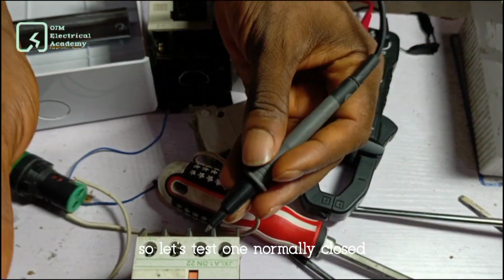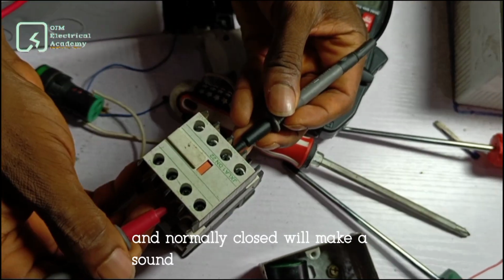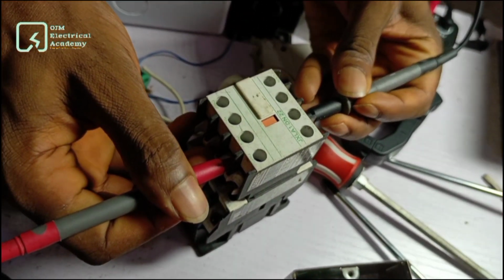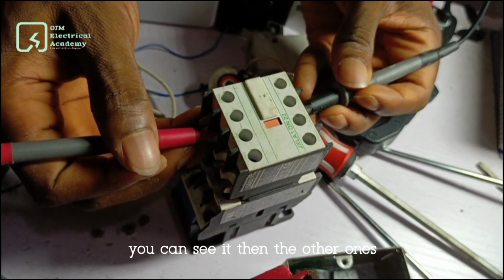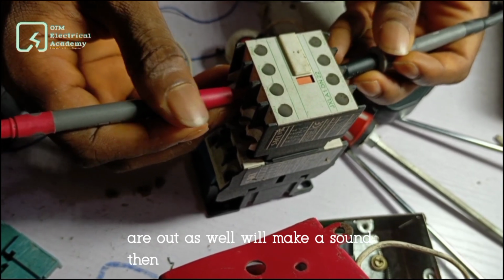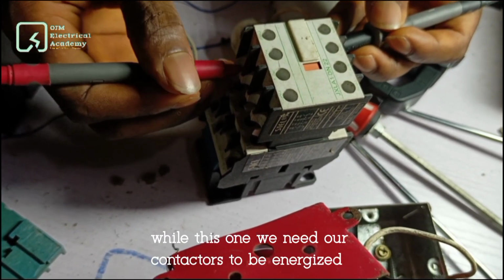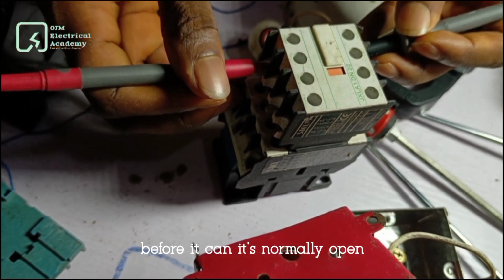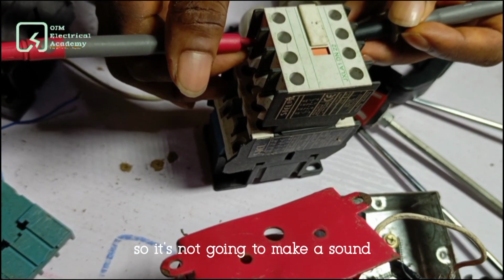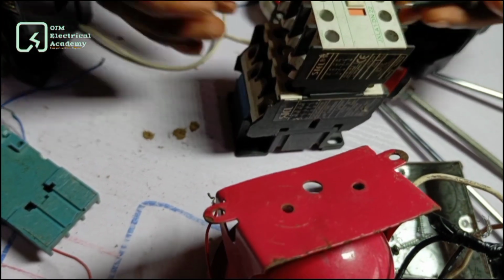Let's test one. Normally closed and normally closed will make a sound, you can see it. The other ones will also make a sound. But for this one, we need our contactor to be energized before it's normally open, so it's not going to make a sound until it comes on.